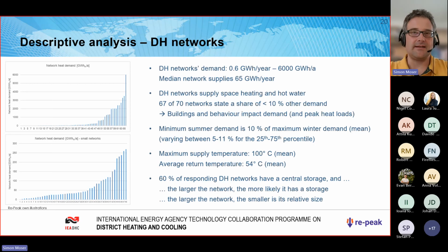We see that the minimum summer demand is approximately 10% of maximum winter demand, varying only a little around that value. Supply temperatures are approximately 100 degrees Celsius in the mean, and average return temperature is 55 degrees Celsius in the mean. Again, be aware of maybe a small bias here by Austrian biomass networks. We especially see, for example, looking at the Danish responses, that temperatures are lower than that.